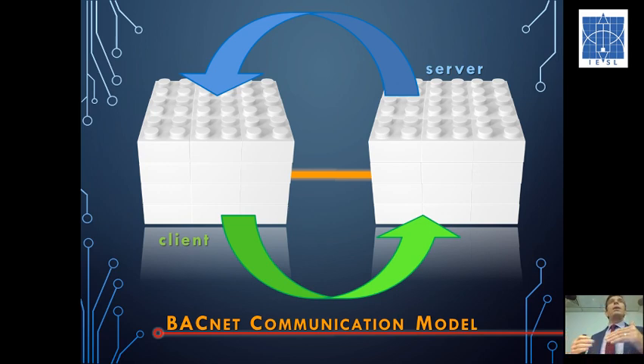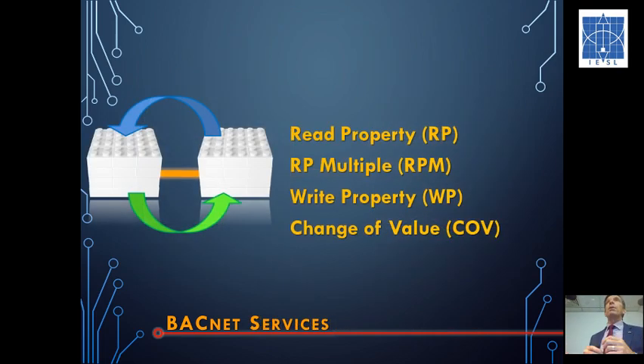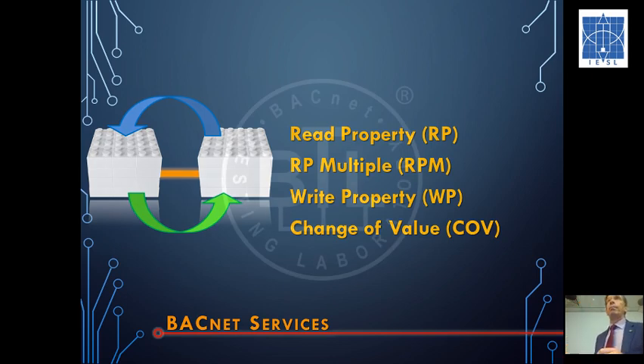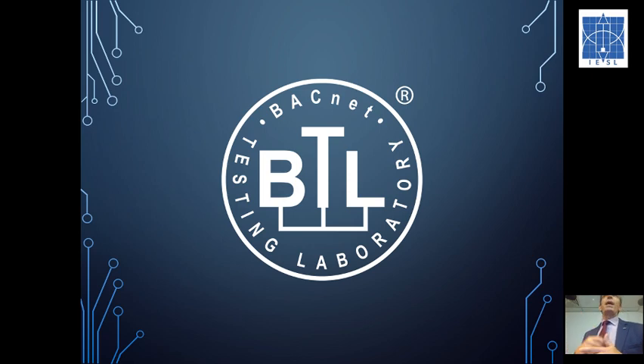And the standard is actually a communication model where I ask a question and I have an answer to that question. So a client will ask a question and a server will answer that question. And these are typical types of services. So a read property or a multiple read property, where I can ask a question of another controller. I might say, what's your temperature? And a single read property will tell me the temperature. Or I may ask a VAV with a multiple request: what's your temperature sensor, your damper position and your airflow. And the device that I've asked a question will answer.